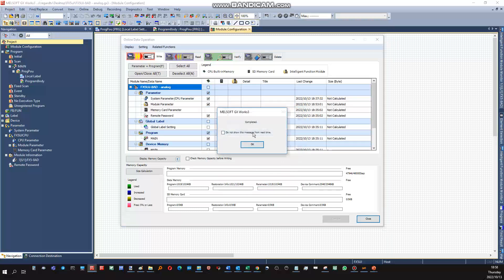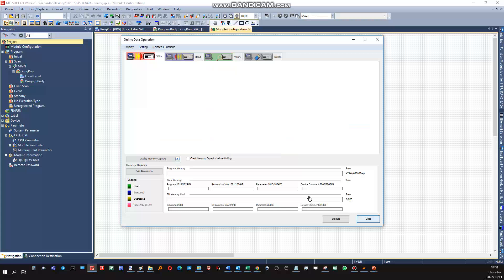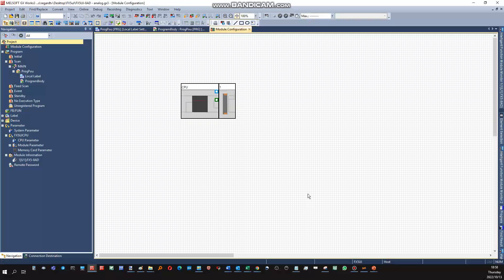After writing to the PLC, you must physically reset the PLC. This can be done either by a power cycle — wait 10 seconds then power back on — or by using the little reset switch on the PLC. An error will pop up showing that the communication is missing; this is normal during a reset. The PLC is put back into run mode, and the setup is done with no errors on the PLC or the program.